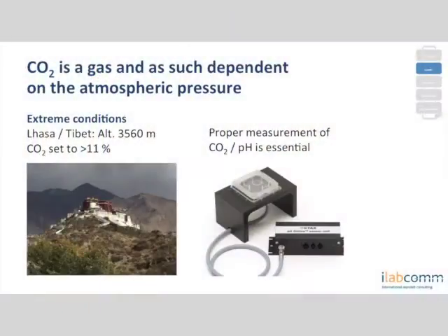Nice example here, which I always like to bring up. Most people don't know that the CO2 is really dependent on where you are. And it makes a difference whether you are, let's say, in Istanbul or Helsinki, where you have actually sea level, or whether you are in Lhasa in Tibet at an altitude of 3,560 meters. There is an embryoscope in this city, and this is running at 11% CO2 in order to have a proper pH in your culture medium. Denver, David worked there, is around 8%, 7%, something like that.